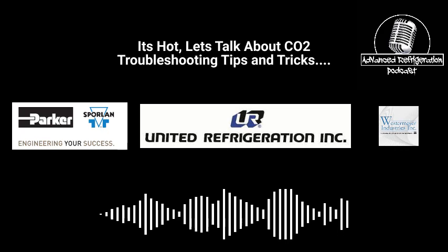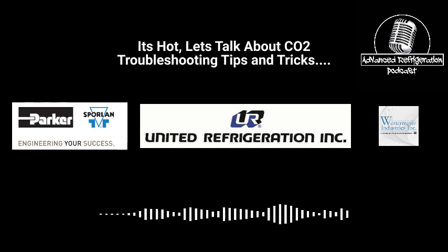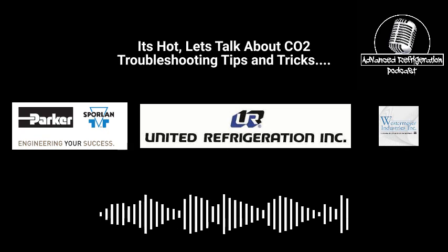If you're looking at the controller, I've seen it done two ways. I've seen that drive a relay that drives the oil drain, which is very archaic. Generally, that's not how it's going to be, but it could be. You need to look at the wiring diagram. Or what usually happens is it goes back to the EMS system, and the EMS system is controlling the oil separator drain. What's happening is you're going to get a dry contact, so a digital input. It's just going to get a closure.